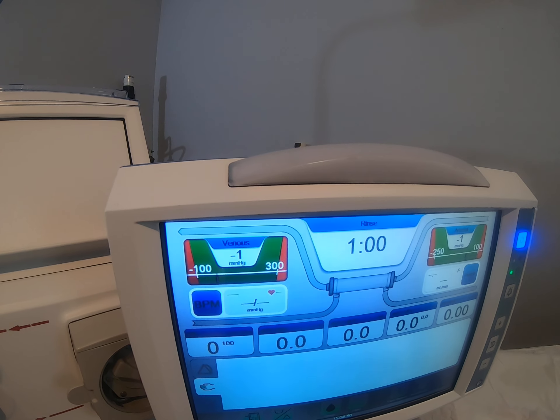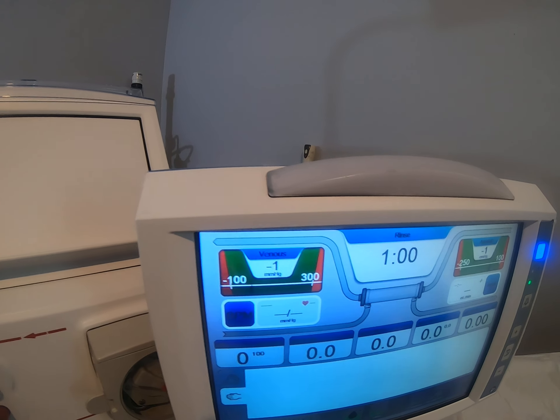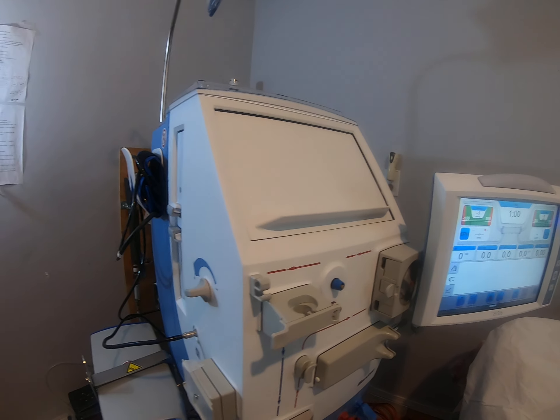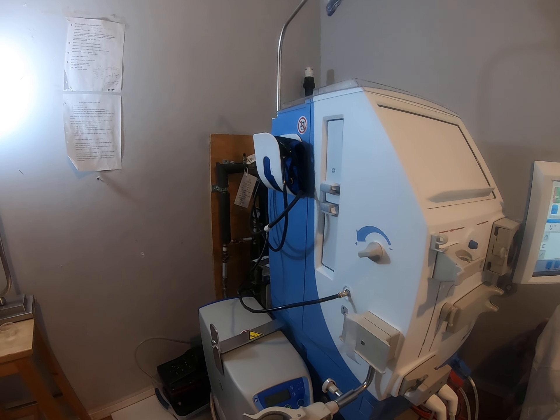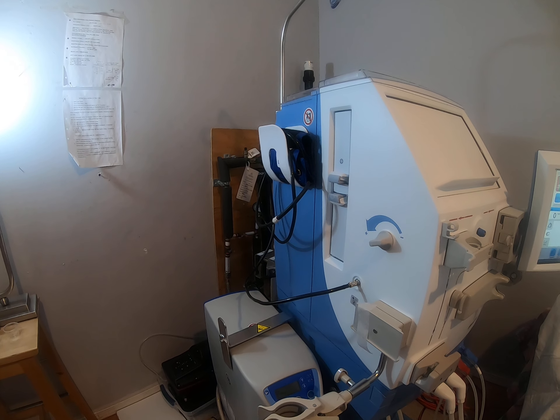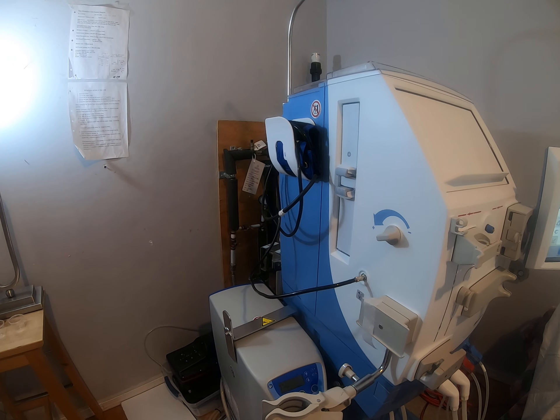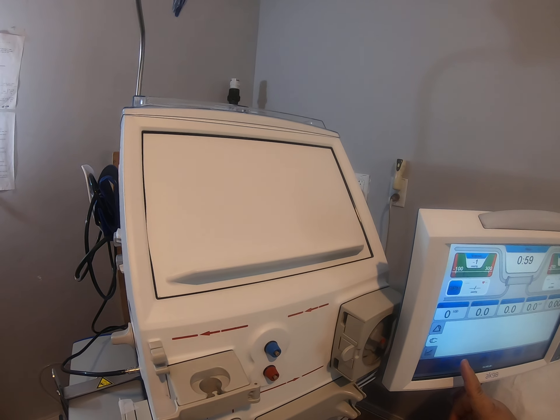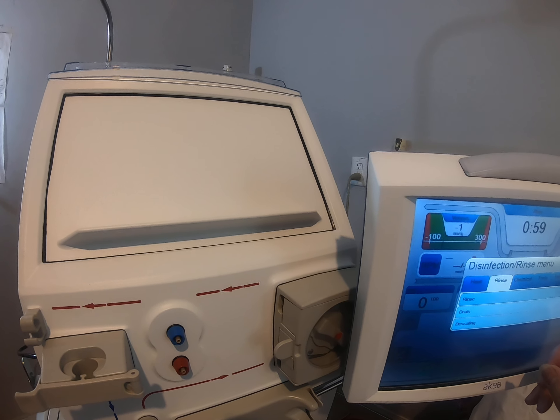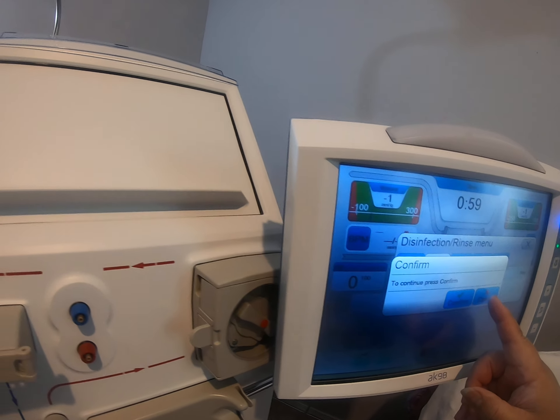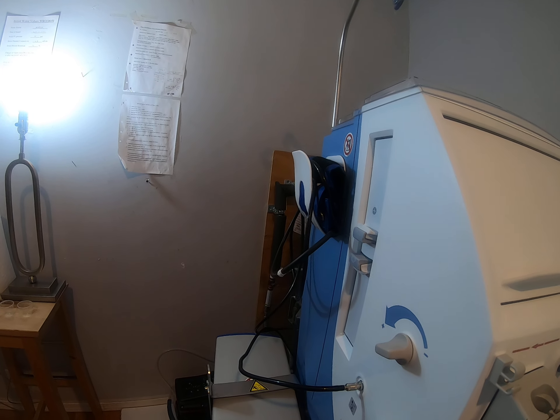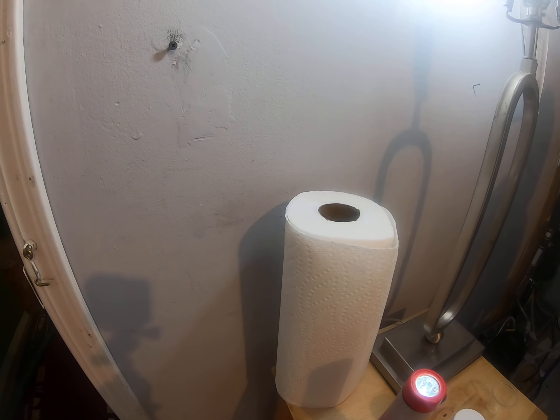We are still waiting for at least two minutes down. We are not going to wait for the 10-minute countdown. There we go — we just start for the purpose of the chlorine check here. We're not going to wait for the 10 minutes, so we will just do our chlorine check. This is only for the purpose of demonstration.